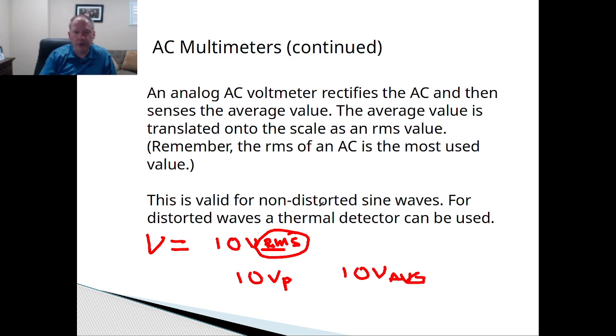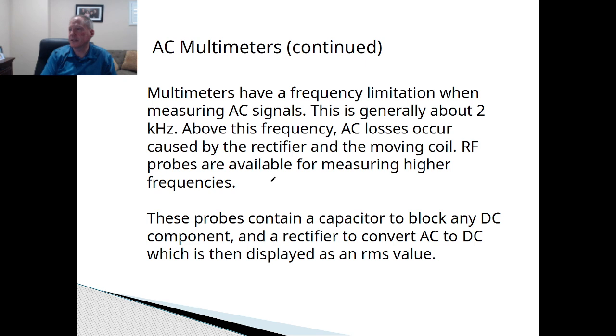Now this is valid for symmetrical waveforms, which means that the top half of the wave is equal to the bottom half of the wave. And sometimes they're not, right? Sometimes they can be distorted. But keep that in mind, the meter is only going to do the average, even if the bottom half is not congruent or equal to the top half.